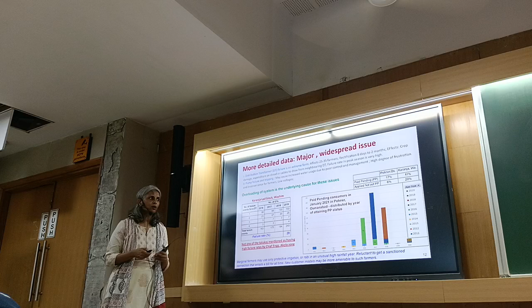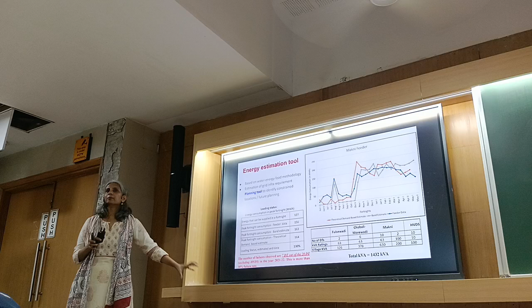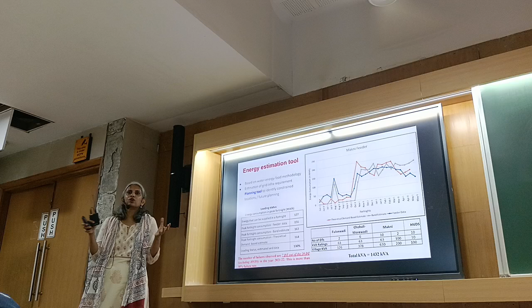So instead of going by connection, what we have done here is this energy estimation tool looks at the cropping and irrigation requirement of an area and hence the distribution transformer capacity required, because the distribution transformer is like a bottleneck. It is also the most expensive part of the system. Every connection costs about 1 lakh, and 30% or more of that cost is the distribution transformer. So what we've done here is to estimate the capacity required in the peak season, because if you satisfy it at the peak season, then you'll be fine for the rest of the year.